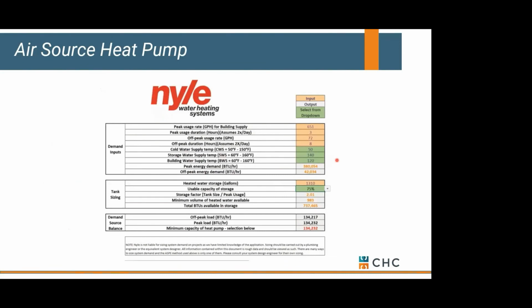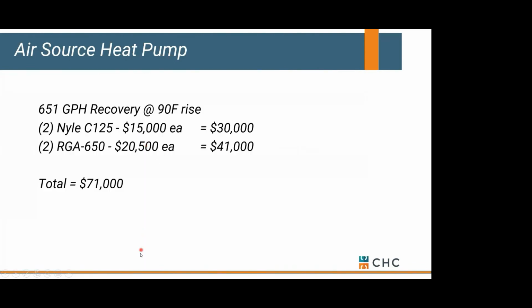We could look at an air source heat pump style water heater. Peak or off peak, if you will, is going to be 8 hours. If you remember from our example, we're going to be looking at a load of about 134,000 BTUs during that off peak time. And what's important here is the storage required is about 1,300 gallons. So heat pumps don't generate a lot of hot water. So they need pretty good sized storage to maintain that throughout the day, depending on your loads. So here we've got two heat pump water heaters and 1,300 gallons of storage, designing for about a 40-degree worst case outside air temperature. We look at some numbers here. We're in at about $71,000.